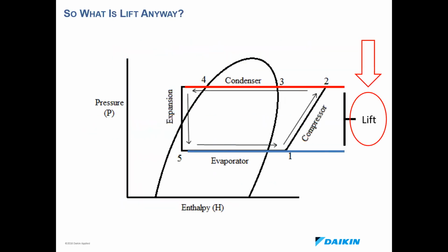So what is lift? I mentioned lift a little bit. Most of you are probably familiar, some may not, but lift is essentially just the difference between your condensing pressure and your evaporator pressure. So the top red line is going to be your ambient temperature. That is part of your condenser coils. It's a function of those.